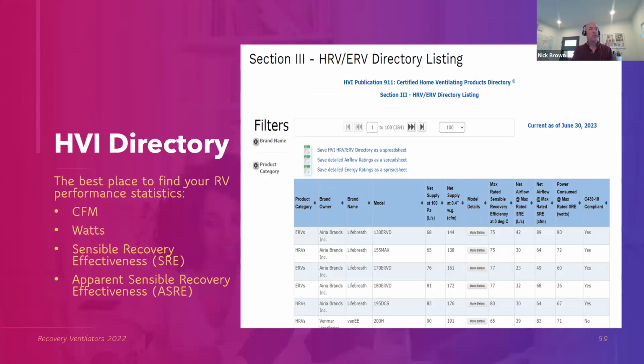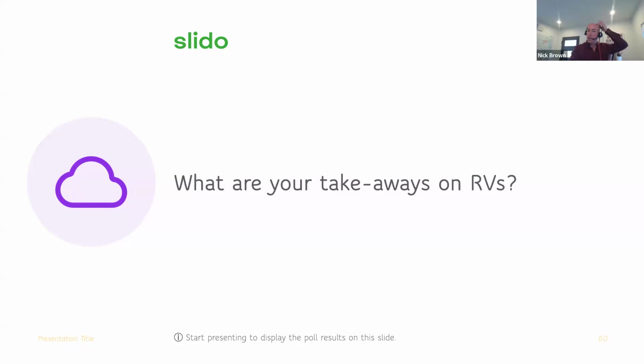Here's a snapshot of the HVI directory. They have this category of HRVs and ERVs, and you can search for all different brands and CFMs and find the recovery effectiveness here. So yes, Jay, ERVs do come with a condensate drain. In my experience, mine isn't creating any condensate. That may just be a function of my climate. So I just have the condensate drain going into a 2-gallon bucket and there's never anything in there. But in some climate zones, you are going to produce that and you're going to need to provide a drain for that.